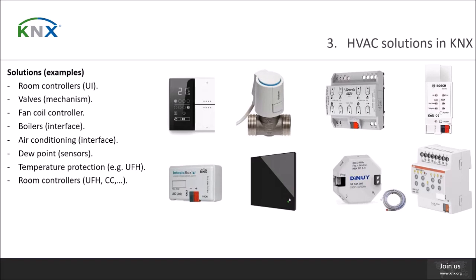Sensors like dew sensors are used in cooling ceilings to detect moisture. Cooling systems tend to create moisture due to condensation, and dew sensors can calculate the dew point given the current conditions and override the cooling system to avoid moisture occurring, which can damage the ceiling. Other sensors, like temperature probes, are used for temperature protection, normally in underfloor heating systems. It avoids damaging the installation if overheating is detected, again, by overriding the control and switching off or changing the set point. Lastly, room controllers, which are multi-purpose devices, normally for controlling the valves of underfloor heating and cooling ceilings with specific HVAC applications.